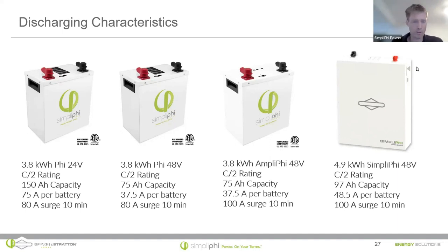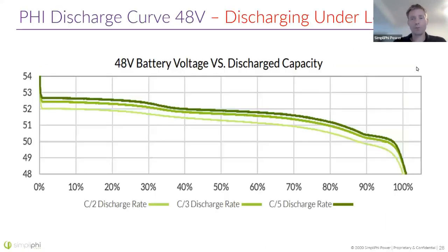The limitation there is really the amount of current running through the BMS. On the AmpliPhi battery with that larger BMS, that battery can surge to 100 amps for 10 minutes. And surging at 100 amps at a voltage above 50 volts, that's 5,000 watts out of a single battery. Now that's limited, right? You can only do that for about 10 minutes. If you do that too long, it'll produce too much heat inside the battery, which can damage it. But there is that surge ability there. And so that's one big difference between the discharging and the charging cycles. All still rated at C/2 for continuous use.